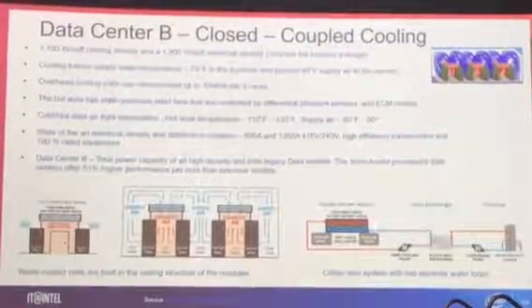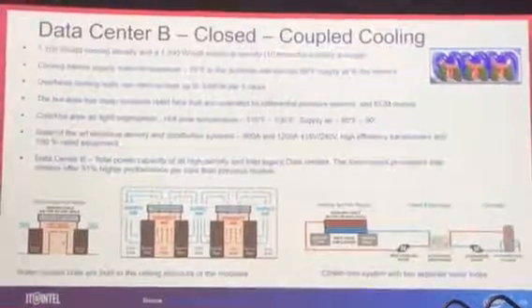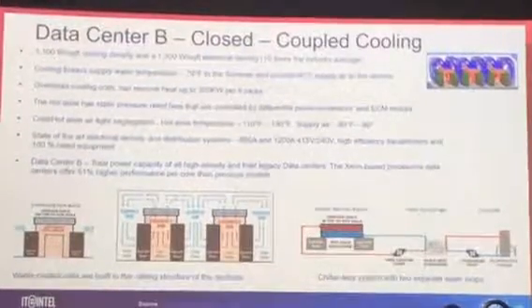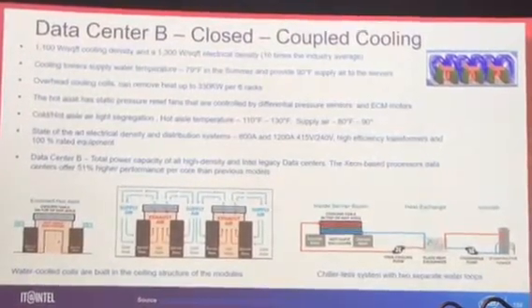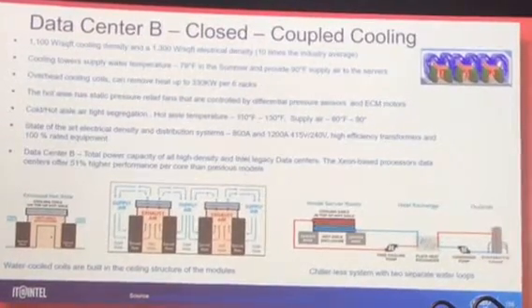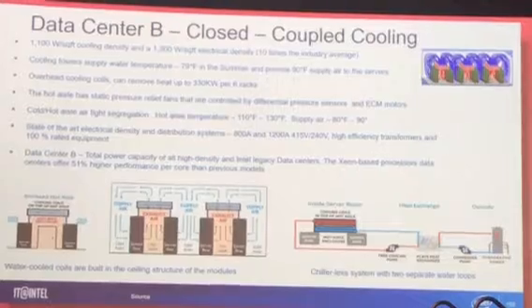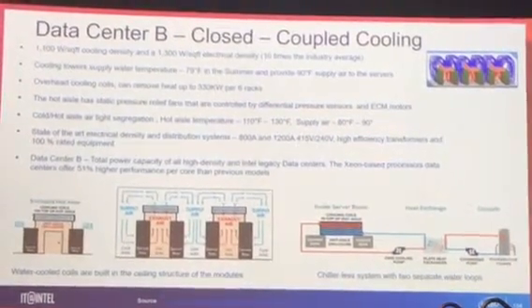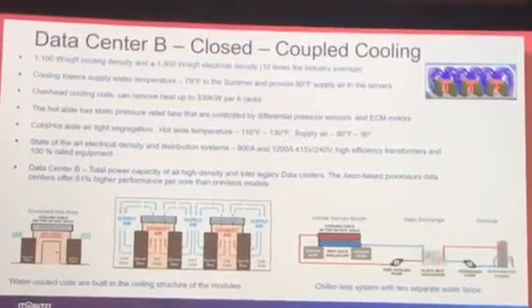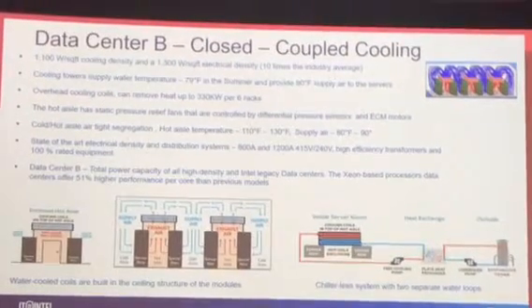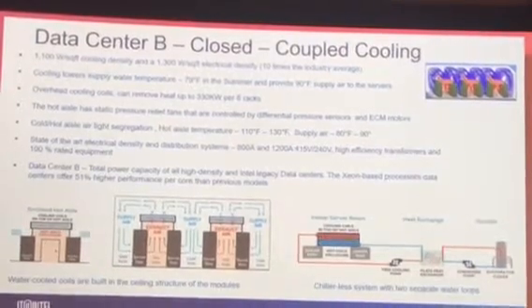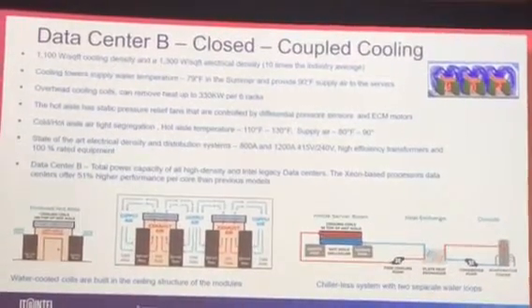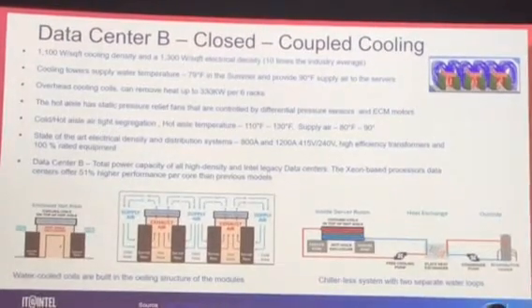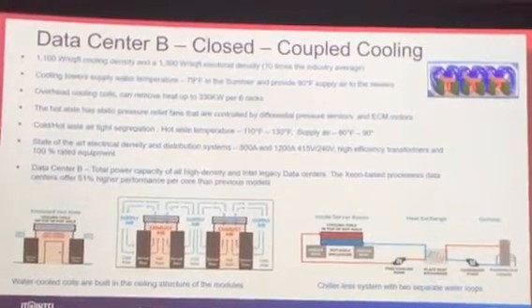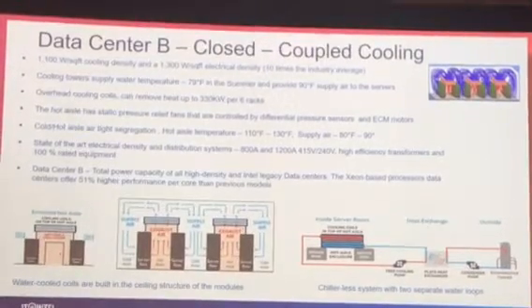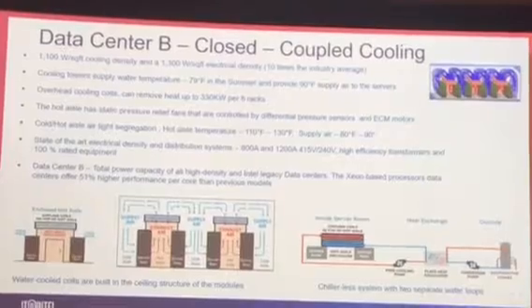The server type in this data center doesn't require any backup system, UPSs or generators. So like I said, we have overhead cooling coils. The coils have ECM motors that change the speed based on the pressure inside the hot aisle. So if there is no load from the servers, for example, then the fan on the coil will reduce the speed. The pressure still stays the same. And when we have higher load on the servers, the ECM fans increase the speed and release the pressure from the hot aisle.